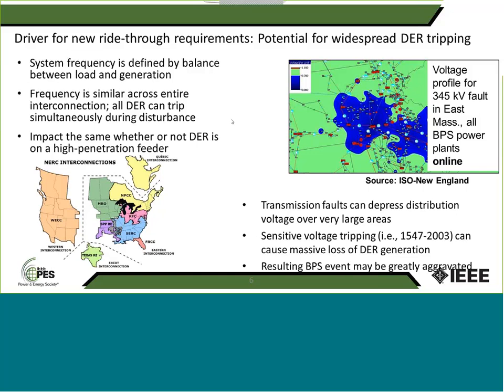Like a delayed voltage recovery. They call it FIDVR, fault-induced delayed voltage recovery. So that undervoltage condition may stay in the grid for a second, 2 seconds, depending on the reactive component, the inductive component of the grid, which can definitely cause DERs to trip. So that's basically the reason that ISOs are concerned, given the fact that we already have high-speed protection on the transmission system. So that's basically the driver.